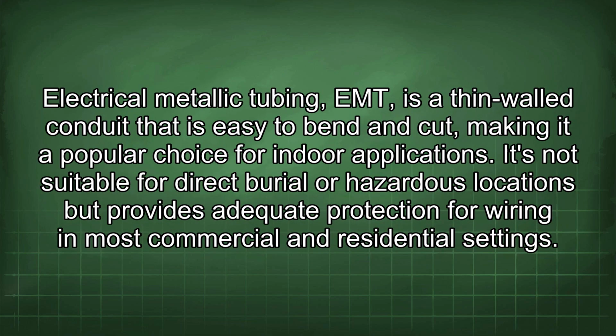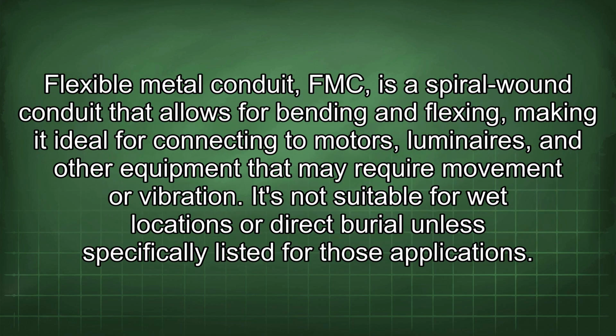Electrical metallic tubing (EMT) is a thin-walled conduit that is easy to bend and cut, making it a popular choice for indoor applications. It's not suitable for direct burial or hazardous locations but provides adequate protection for wiring in most commercial and residential settings. Flexible metal conduit (FMC) is a spiral wound conduit that allows for bending and flexing, making it ideal for connecting to motors, luminaires, and other equipment that may require movement or vibration. It's not suitable for wet locations or direct burial unless specifically listed for those applications.